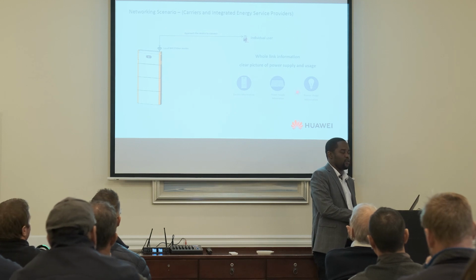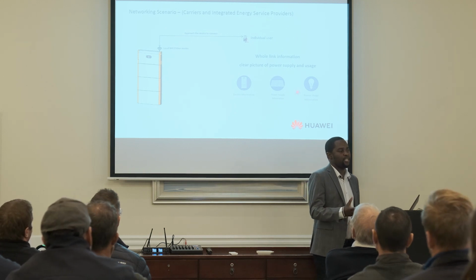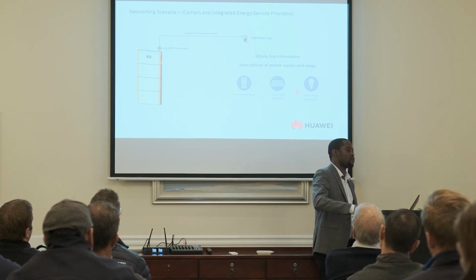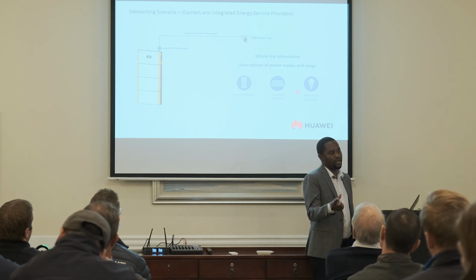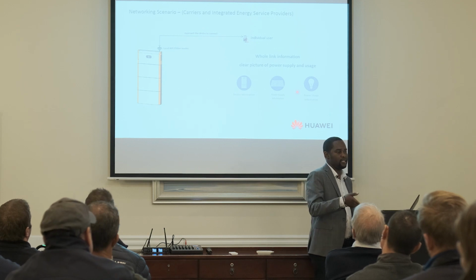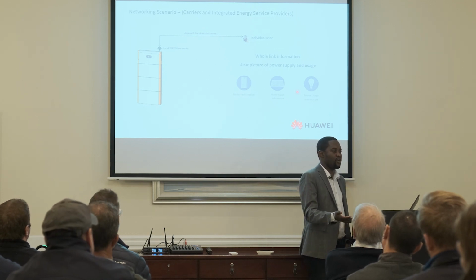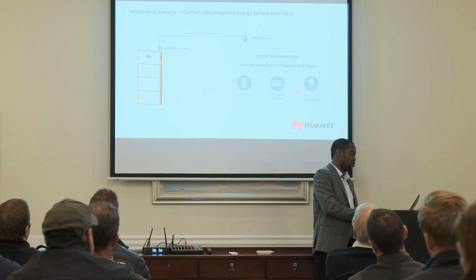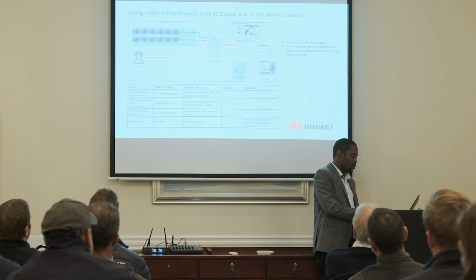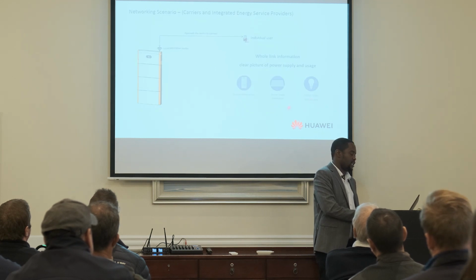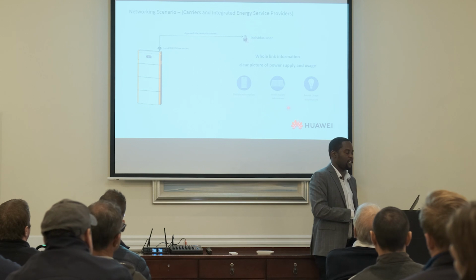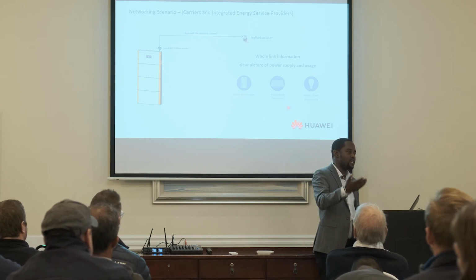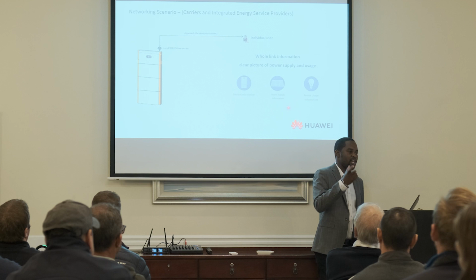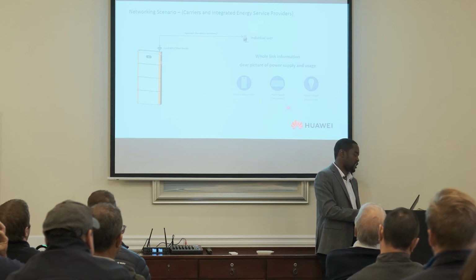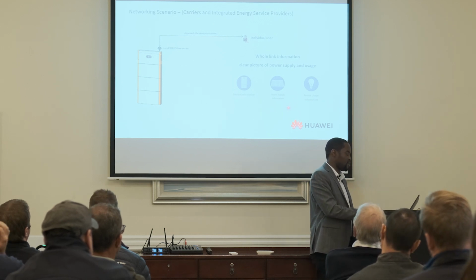Then the systems used to be on NetEco, because on Huawei's divisions, this was for the site power, so it was in telecommunications. That's why from about 2 months ago, it was still on NetEco, but now it has been moved to FusionSolar, which is the power division of Huawei. So on FusionSolar now, you can open the account, then you've got end users. They can also get reports from their system. They can get the summary of what they've used from grid. They can get the summary of their yields, what they've used from their batteries, how many hours the generator has run, and what they've used from the generator, and device information and alarms, right?